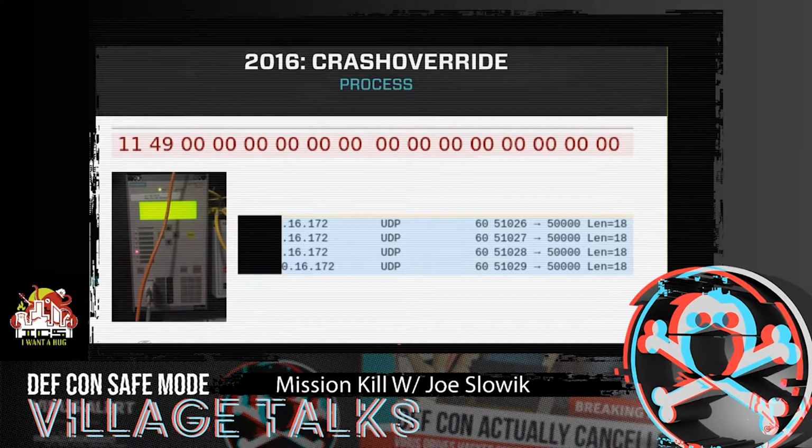It is worth noting that there was an endianness mistake in the malware. Not sure if they were counting on this being translated in some fashion, although working in a lab environment, not quite sure how this was supposed to have worked, but it doesn't look like the payload would have been delivered properly, at least in the actual attack. And this was one of a number of mistakes that were made as part of the CRASHOVERRIDE event.